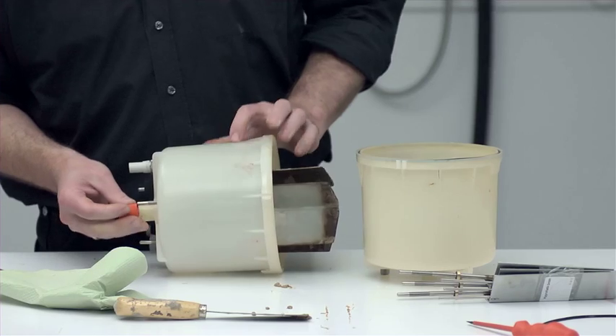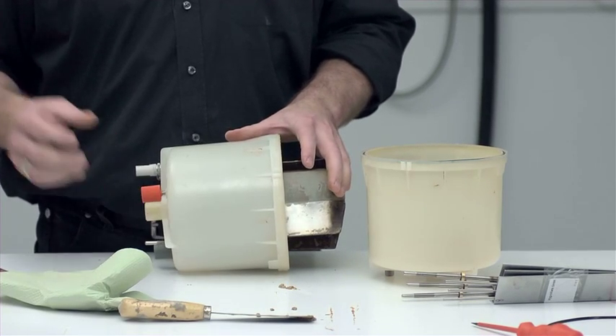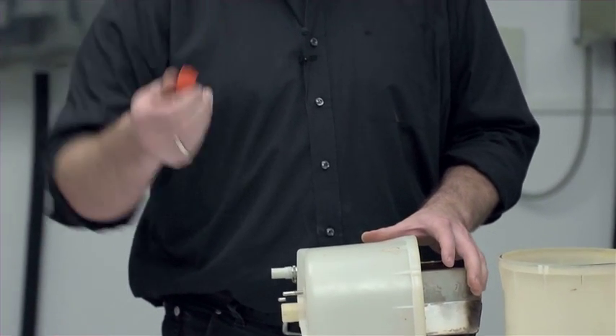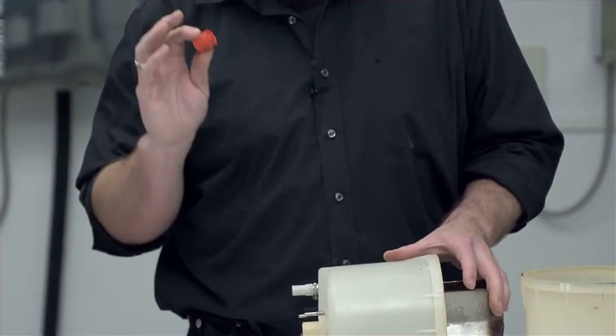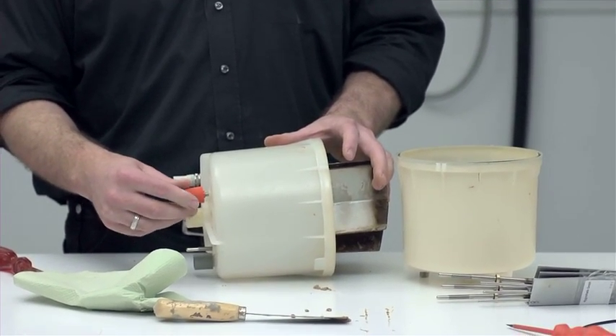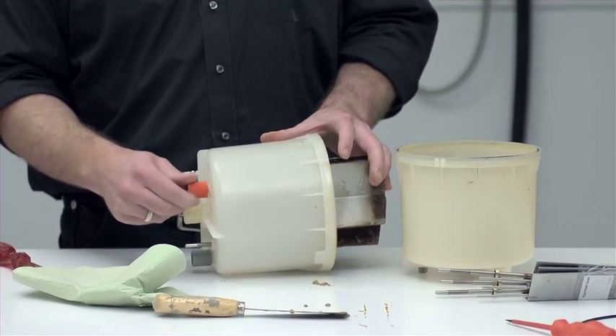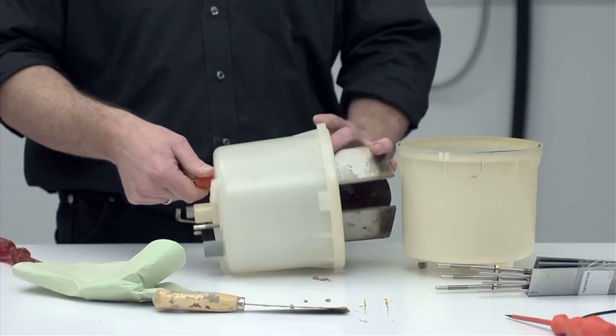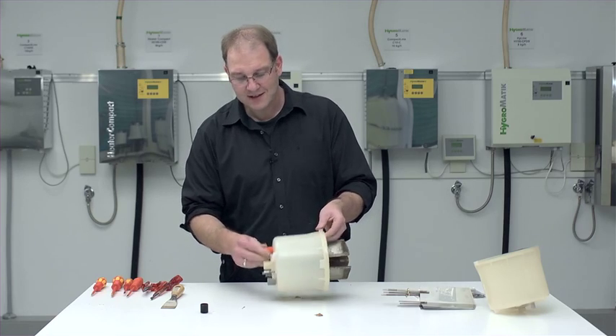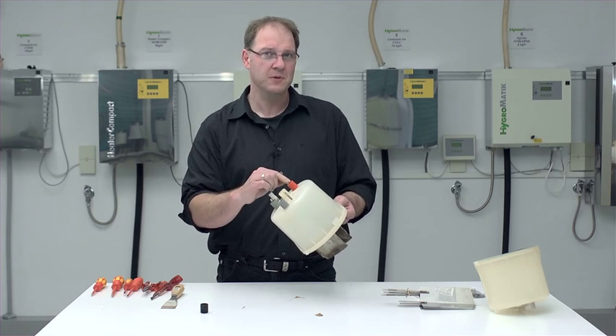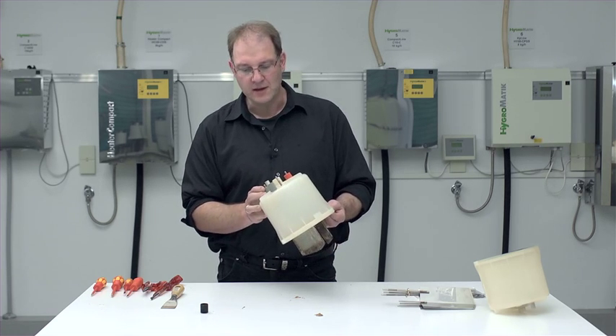Now simply screw on the knurled nuts or hand nuts and please take the term hand nut literally. We have designed them to be tightened solely with manually applied force. Please do not use any tools, otherwise you would generate too much force. When using a unit with three electrodes, it is quite optional where the colors go. When using a cylinder with six electrodes, please take care to place same colors at the same phases on opposite sides of each other.